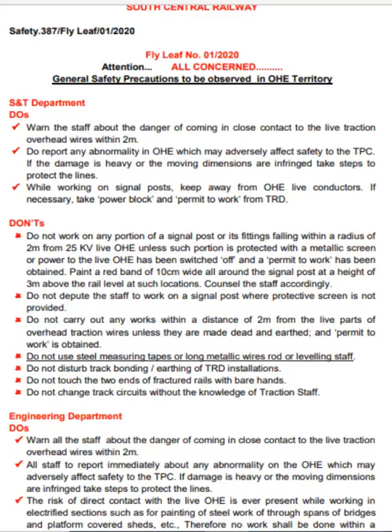Don'ts: Do not work on any portion of a signal post or its fittings falling within a radius of 2 meters from 25 kV live OHE unless such portion is protected with a metallic screen or power to the live OHE has been switched off and a permit to work has been obtained.